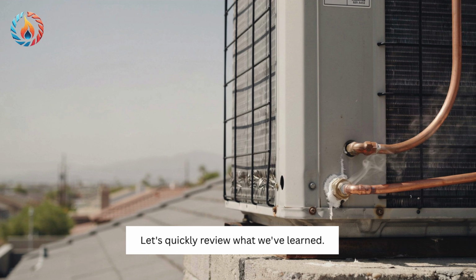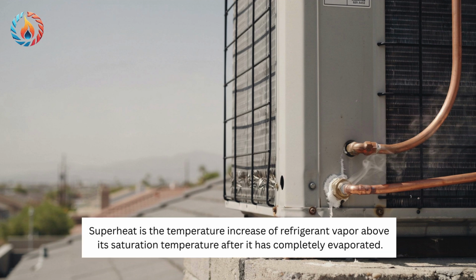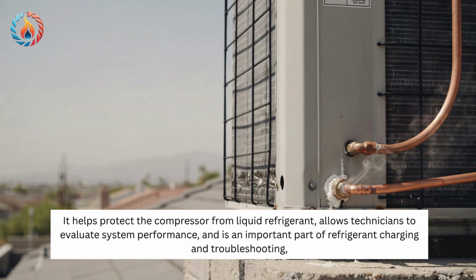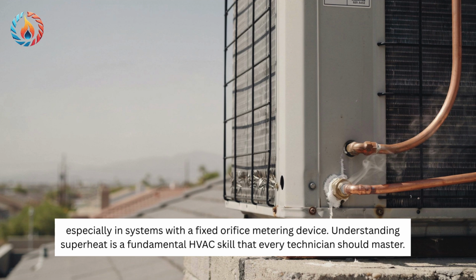Let's quickly review what we've learned. Superheat is the temperature increase of refrigerant vapor above its saturation temperature, after it has completely evaporated. It helps protect the compressor from liquid refrigerant, allows technicians to evaluate system performance, and is an important part of refrigerant charging and troubleshooting, especially in systems with a fixed orifice metering device. Understanding superheat is a fundamental HVAC skill that every technician should master.